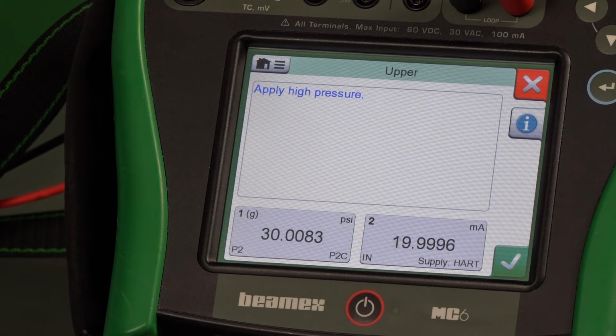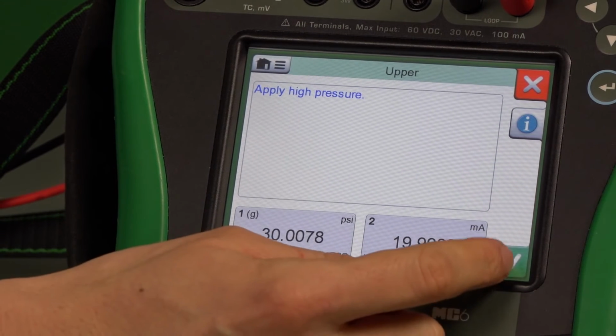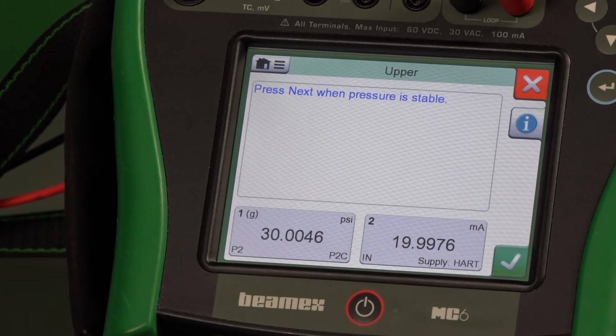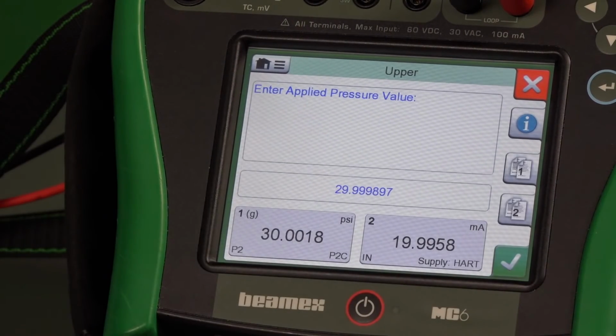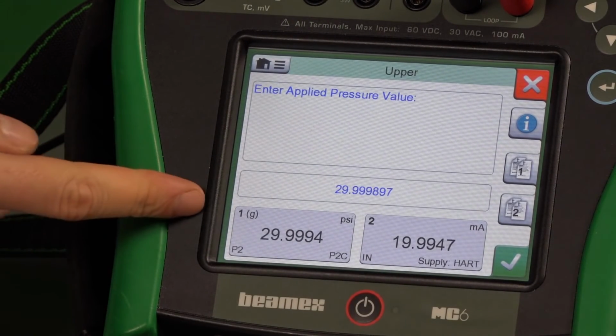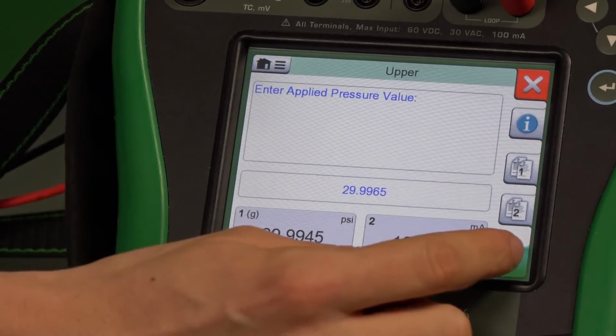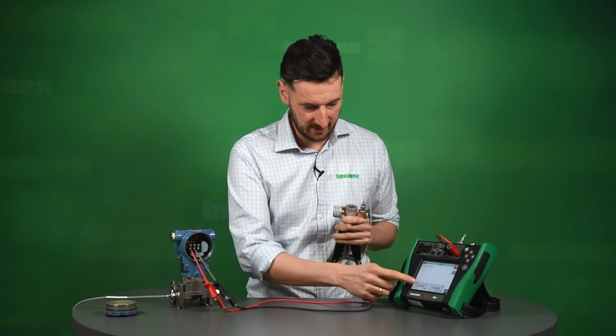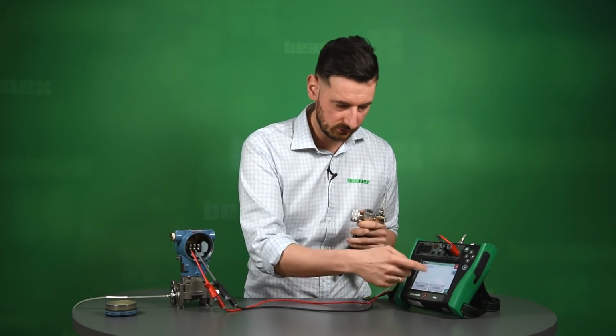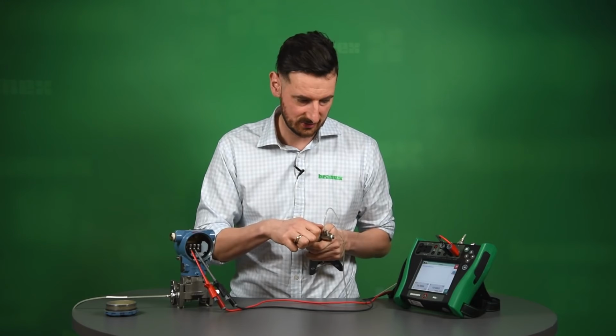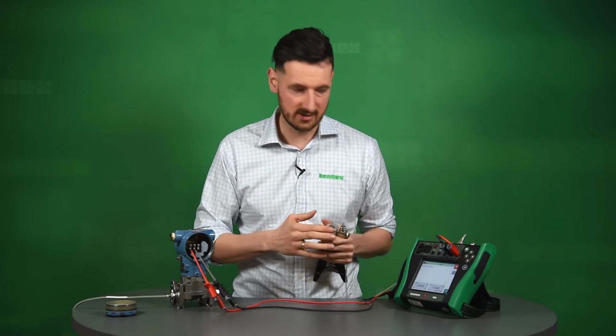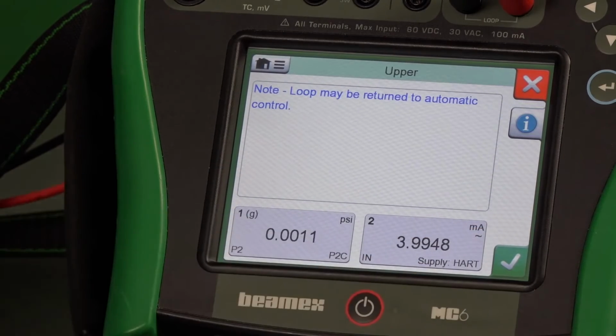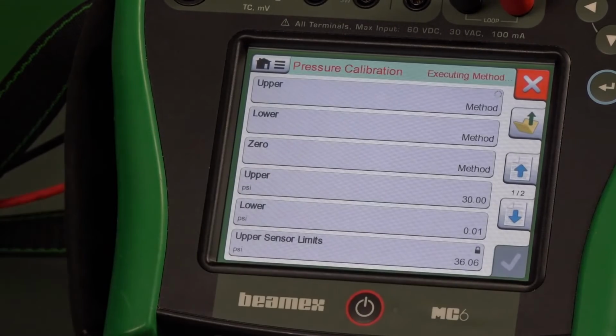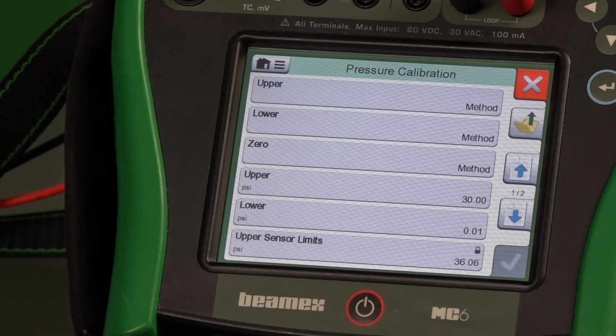It's probably fine. Okay, so you can see right now it's asking us to apply high pressure. We just did. Click OK. And it's actually asking us to copy this value into the field. So that's what we're doing. We're copying the value from one unit to what it asks us to do, and right now it asks us to remove the pressure. So it looks as if that upper trim was successful.